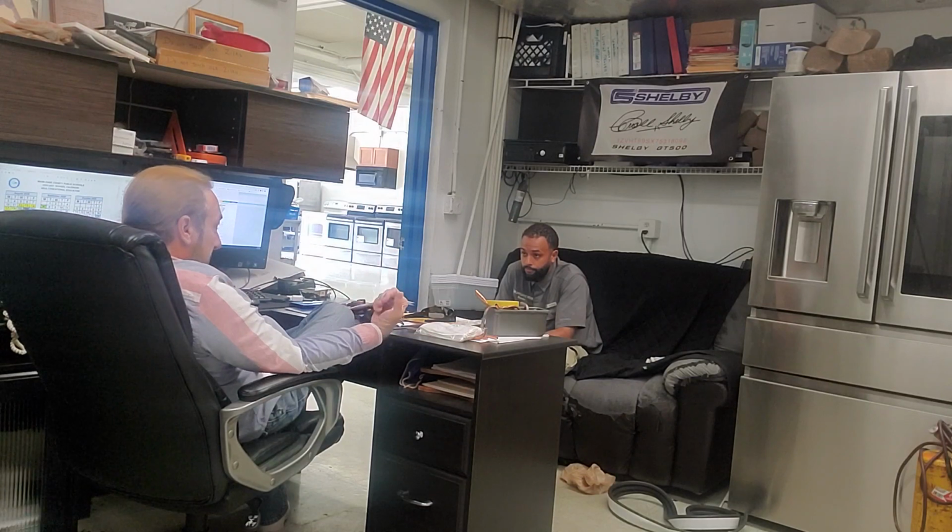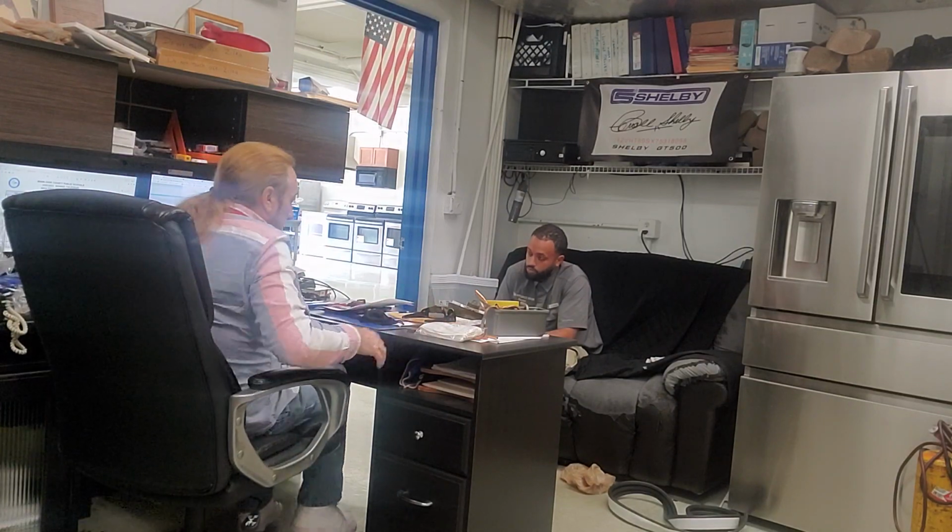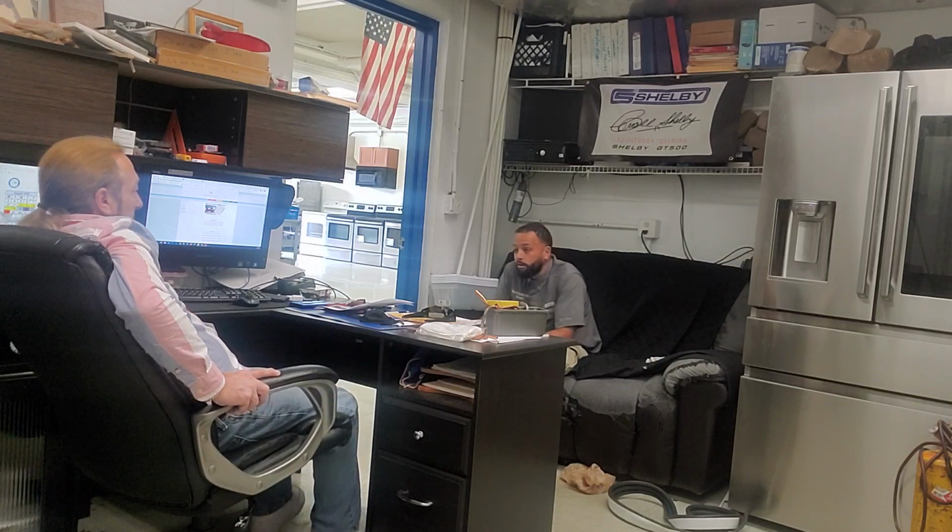Yes, recovery. Recovery first. How to set up the recovery machine, how to use the recovery machine, how to check the gauges and everything. After recovery, we'll show them how to do the actual steps. Now that all the freon's out of the system, we'll show them replacement of the components. Replacement of compressor, dryer filter, even capillaries. We'll show them how to run them down the drain.